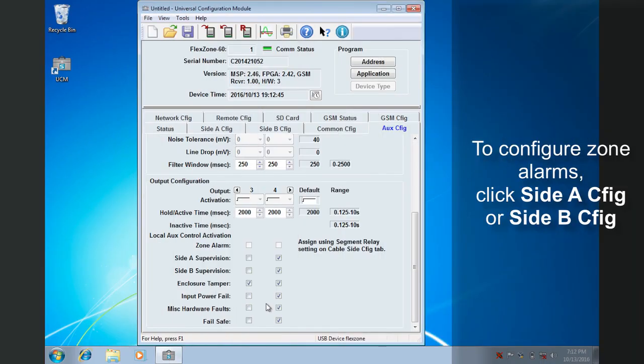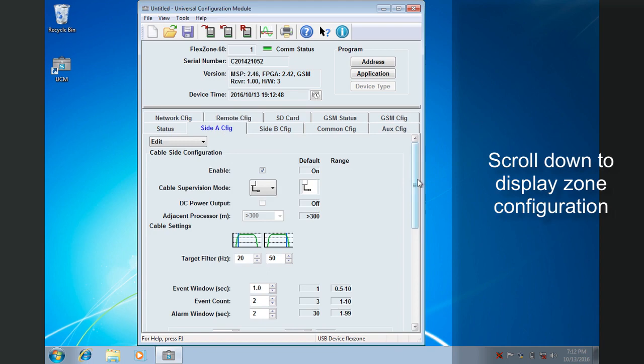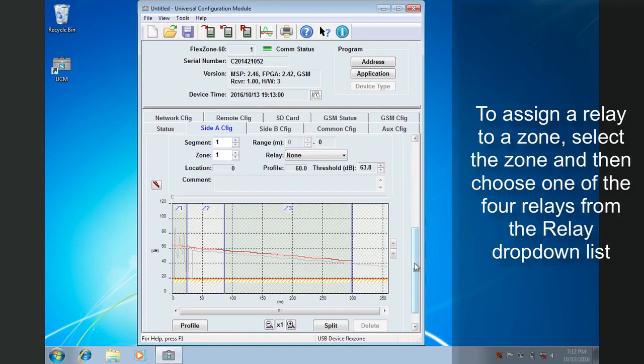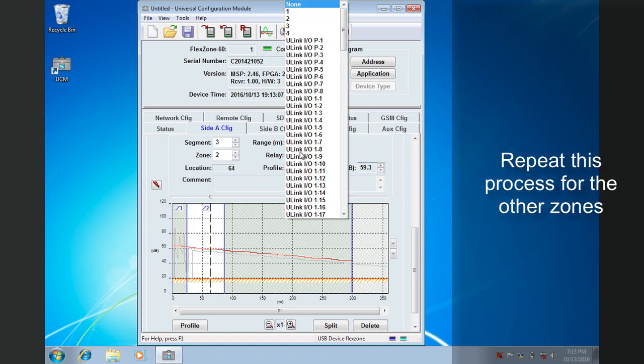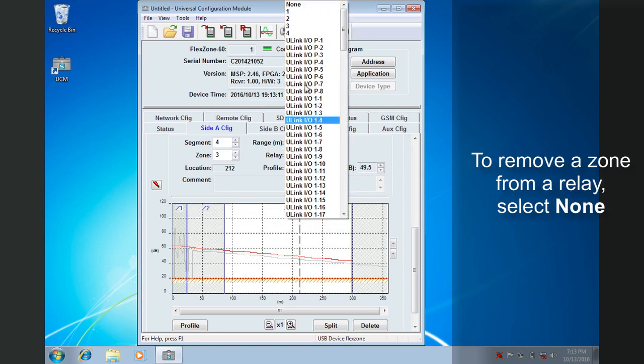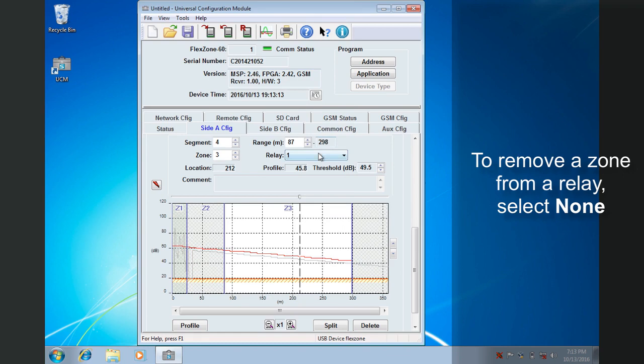Zone alarms are configured separately. To configure zone alarms, click Side-A Config or Side-B Config. Scroll down to display the zone configuration. To assign a relay output, select the zone, then choose one of the four relays from the Relay drop-down list. Repeat this for each zone you want to assign. To remove a zone from a relay, select None.